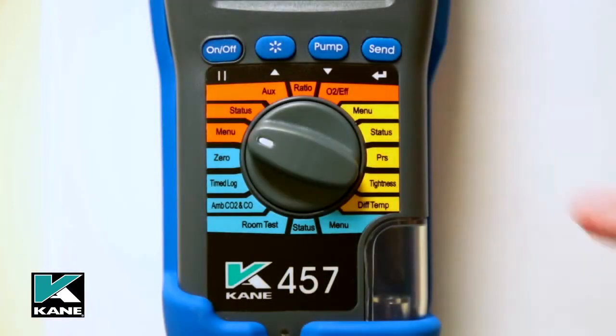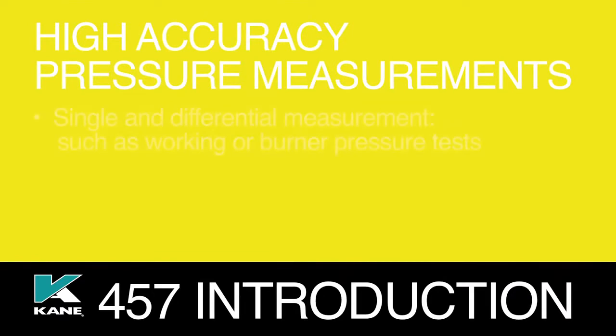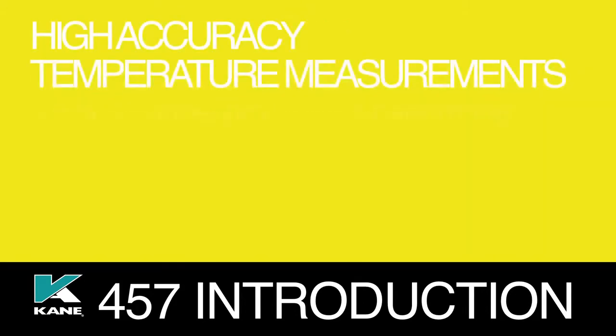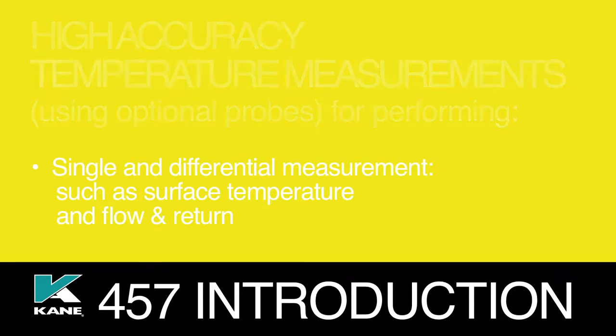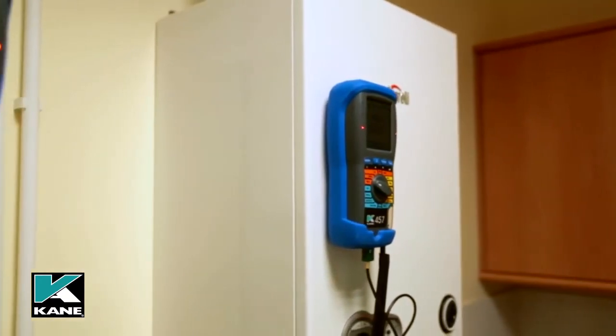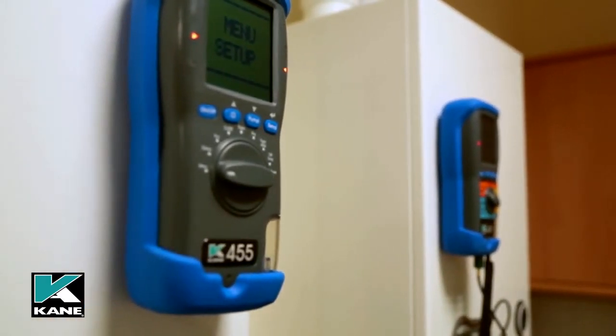The yellow section is for use as a differential pressure and temperature meter, combining high accuracy pressure measurement for performing single and differential measurements, temperature measurement, timed let-by, stabilisation, and tightness tests. With high accuracy temperature measurements using optional probes for flow and return tests. All of these functions — flue gas analysis, temperature, and pressure measurement — are also functions of the Kane 455.